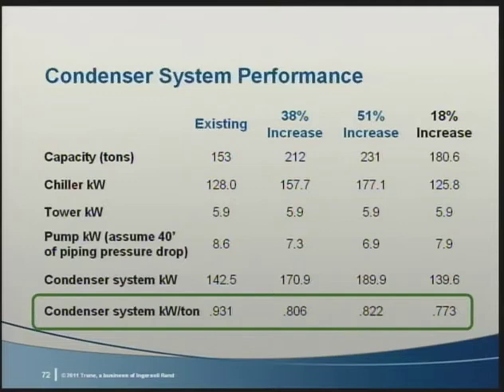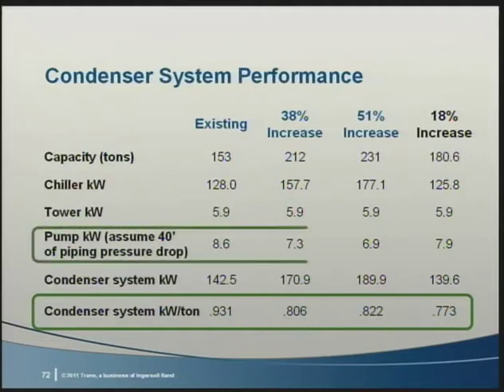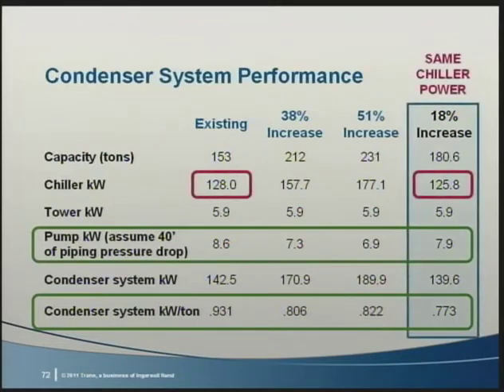But make no mistake, as the capacity rises, so does the demand and the energy the system will use. But due to the new, more efficient chiller, the system is still more efficient from a kW per ton perspective than when it had a 20-year-old chiller. Before we move on, let's look at one more thing. What if our electrical capacity was limited? How much more cooling could we install for 128 kW of chiller power?